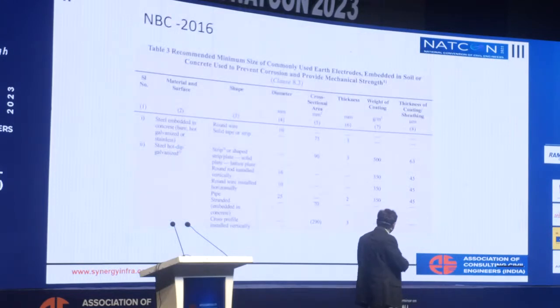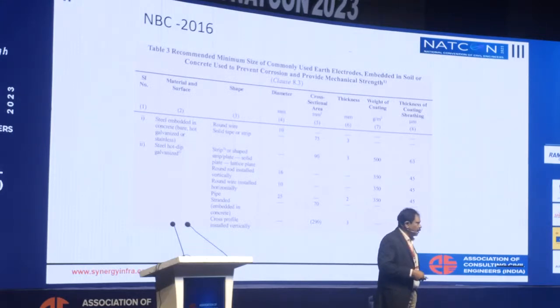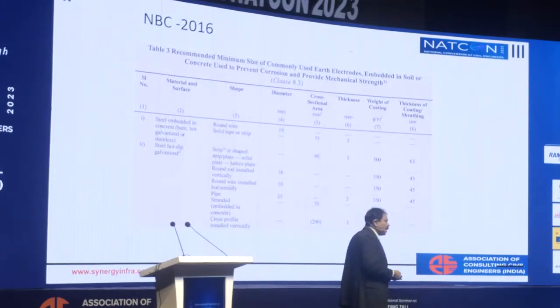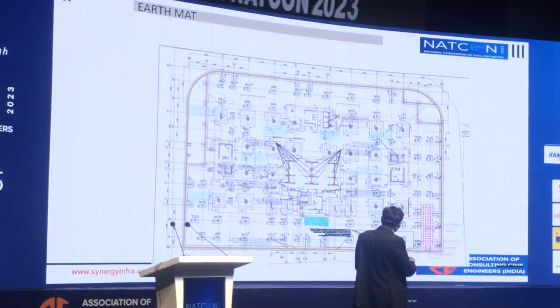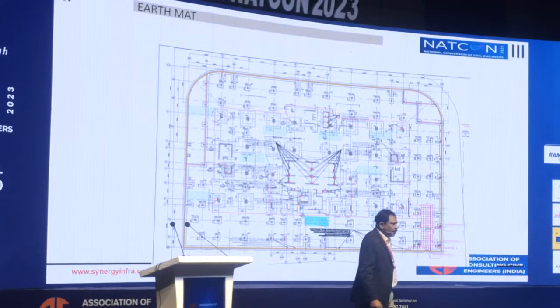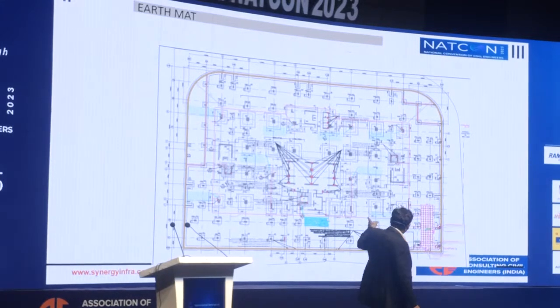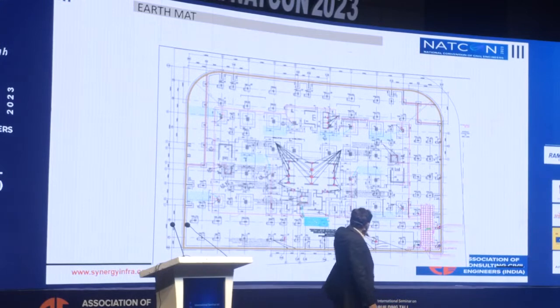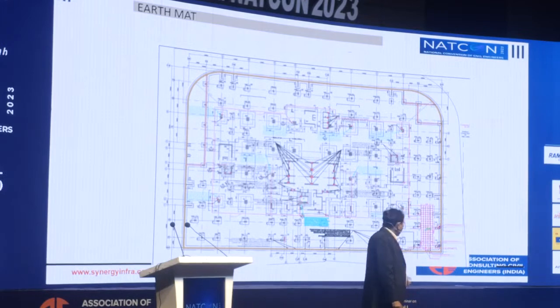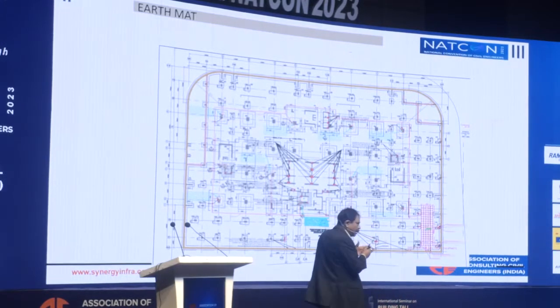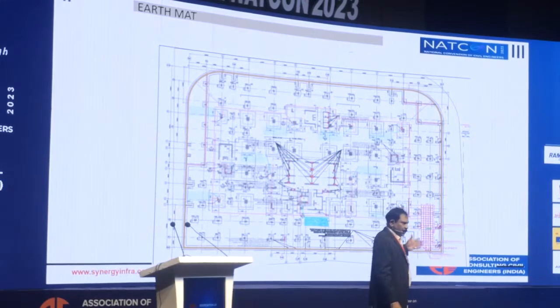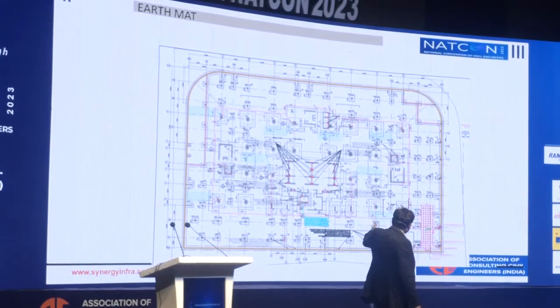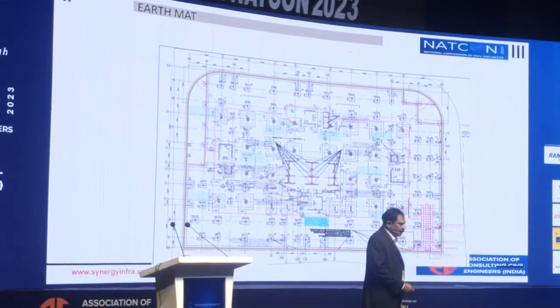Also, the kind of wires or strips to be used as part of the concrete encased electrode could be a 10 mm wire, which by itself is sufficient, basically for bonding to the steel, nothing else. This is one of the basements, which has different earth struts brought out from the raft of the building itself. Wherever we have isolated footings, we have created an earth mat, and all these footings have been interconnected with the earth mat, as well as within 20 meters separation, basically for lightning protection. That is what IEC 62305 says. You need to have a ring conductor and again connect back to the same earthing mat.